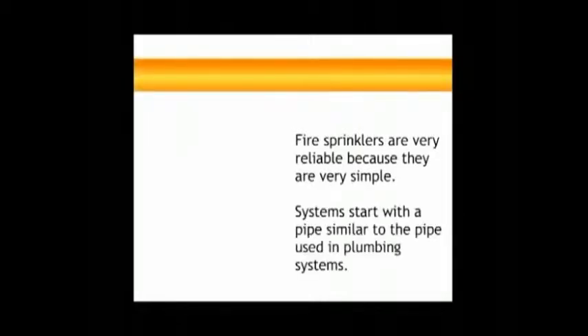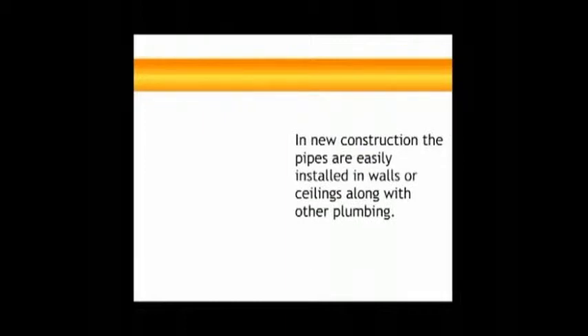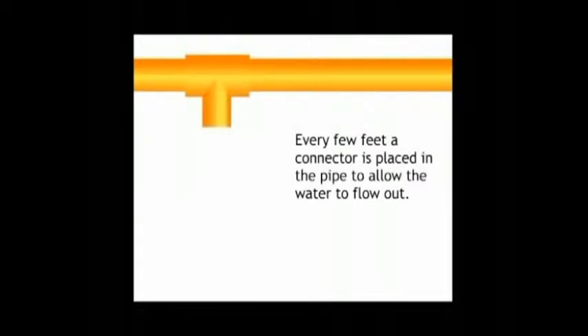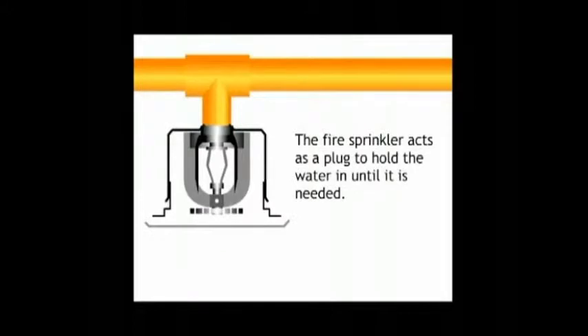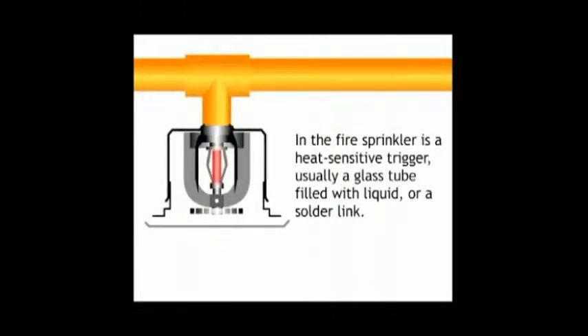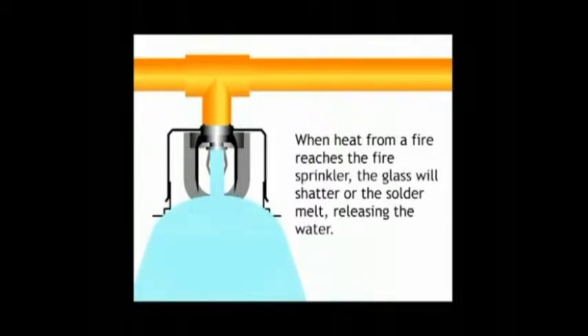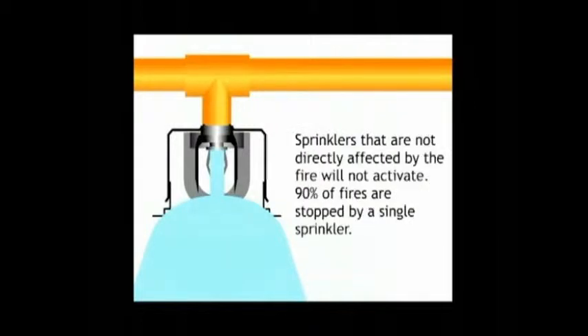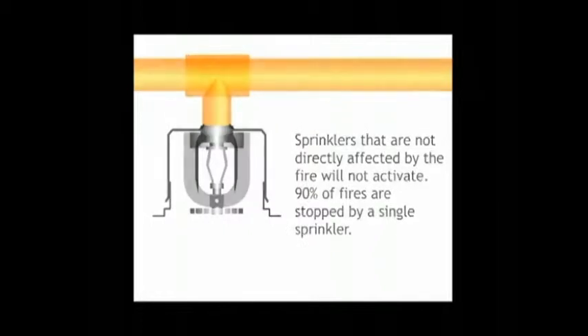This is an example of how home fire sprinklers work. Fire sprinklers are very reliable because they are very simple. Systems start with a pipe similar to the pipe used in plumbing systems. In new construction, the pipes are easily installed in walls or ceilings along with the other plumbing. Every few feet, a connector is placed in the pipe to allow the water to flow out. The fire sprinkler acts as a plug to hold the water in until it is needed. And this fire sprinkler has a heat-sensitive trigger, usually a glass tube filled with liquid or a solder link. When heat from the fire reaches the fire sprinkler, the glass will shatter or the solder link will melt, releasing the water. Sprinklers that are not directly affected by the fire will not activate.